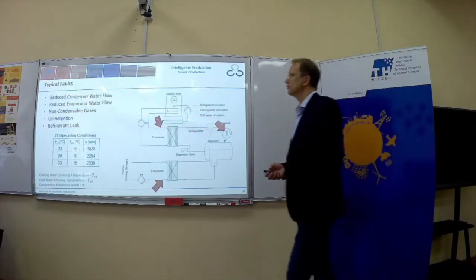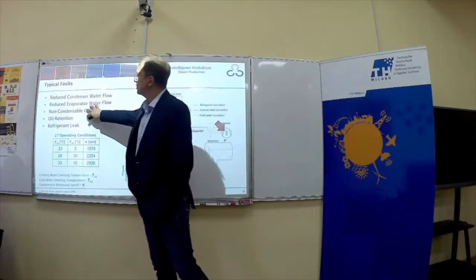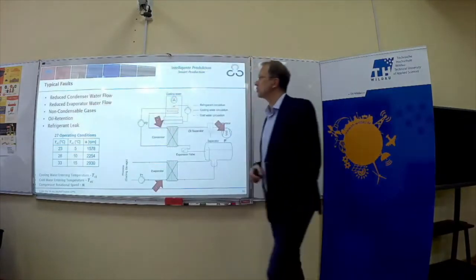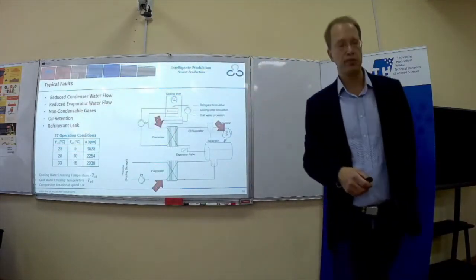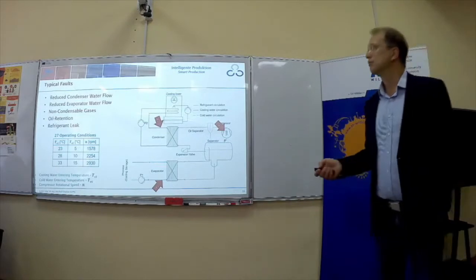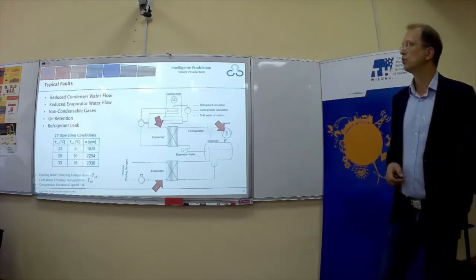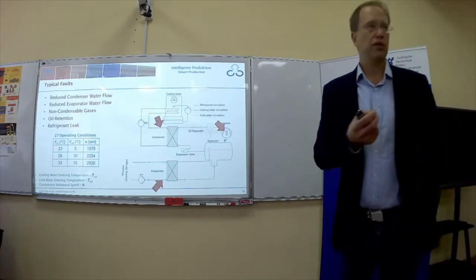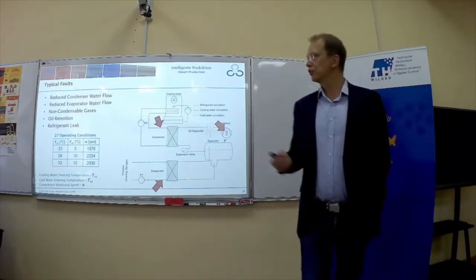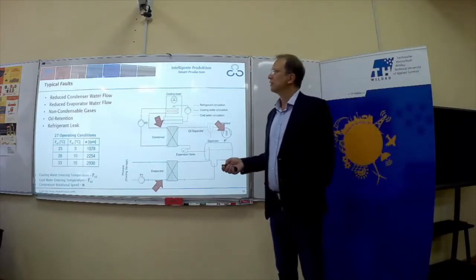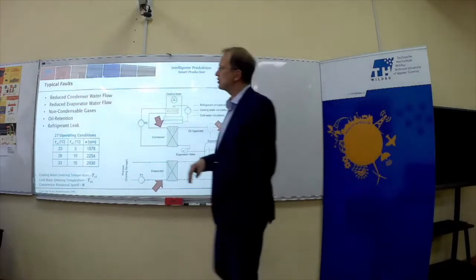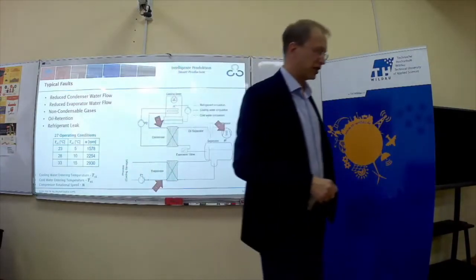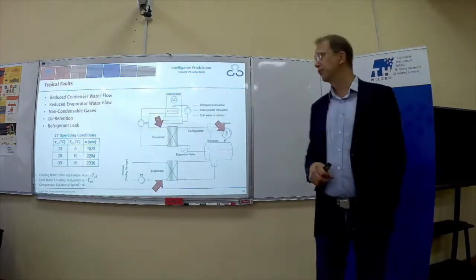Here the faults are written. We have reduced condenser water flow, we have water flow also in the evaporator, as well as the most important thing, oil retention, where we have to see whether the tubes are still usable or not, so that if that feature is not well equipped, we have a capacity loss of over 30, 30-40%.